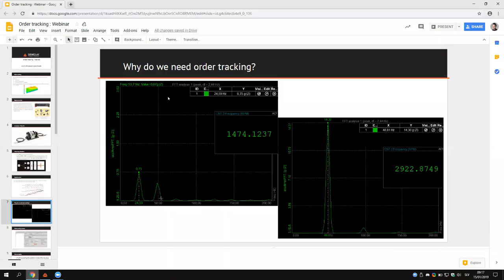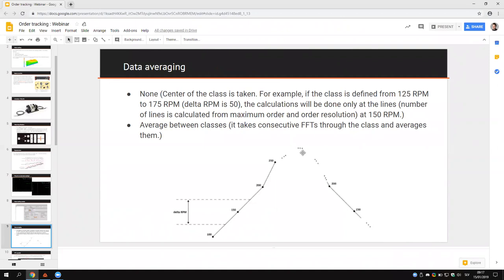To explain data averaging: if we select 'none', the center of the class is taken — no averaging. For example, if one class spans 125 to 175 RPM and no averaging is selected, the FFT is taken at around 150 RPM. But if we select 'average between classes', we make an average within that class and that becomes the displayed FFT.